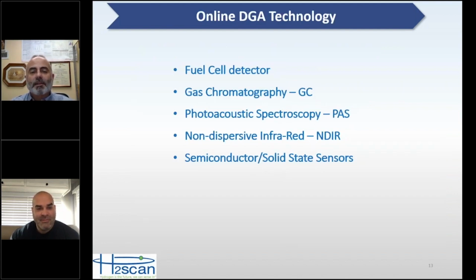So now I'm going to talk about the various technologies that are used, and we'll talk about fuel cells, probably definitely the most popular original online monitor out there. The gas chromatography, so that is lab technology, but some vendors have monitors that are actual gas chromatographs that are able to survive in the field, and those are very nice because they generally match lab values very closely. Then we'll talk about photoacoustic spectroscopy. There's a couple vendors out there that are using that technology, and those are also very popular. Kind of a newer technology for transformer monitoring, but not that new. It's been around a long time, but has been gaining popularity, is NDIR, or infrared spectroscopy. So we'll talk a little bit about that, and then of course we'll talk about solid state sensors or semiconductor sensors.